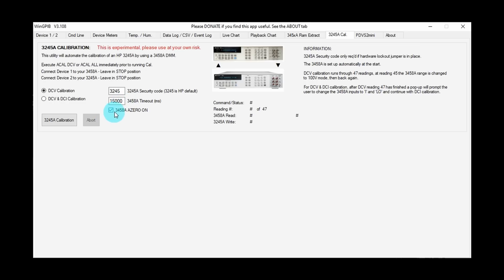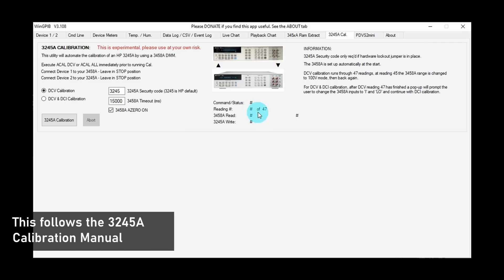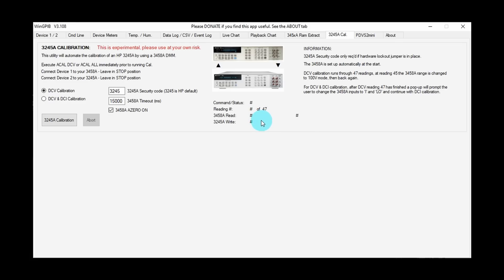In this particular case, I'm only going to do DCV calibration. There's two auto calibrations available—DCV only, and DCV and DCI, and that accounts for the full calibration of the 3245A. But we're just going to run with DCV, and what it'll do is over here it'll run through 47 tests. It will send 47 different voltages to the 3458A, get the reading back, and then make the necessary adjustments within the 3245A to set the calibration. There will be multiple reads on the 3458A—that's my own choice, and that was just to get as stable a reading as possible.